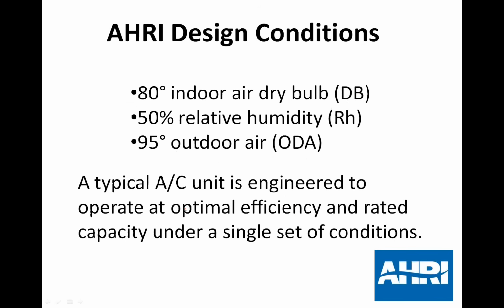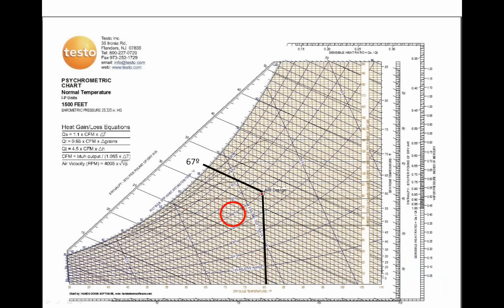When we look at ARI design conditions, okay, a fixed orifice system is engineered to operate under one set of conditions, just one set, that's it. 80 degrees indoor dry bulb, 50% relative humidity with 95-degree outdoor air entering a condenser. And that's the only target that the manufacturer has to engineer that system to operate under. So typically, those systems will operate a little over capacity or a little under capacity depending on the load conditions. The only time they'll operate at their optimal capacity is when they're running about 10 to 12 degrees of superheat at the evaporator coil. If they're not running near that 10 to 12 degrees of superheat, it's operating at a different capacity than it was engineered for. Now, that doesn't mean that it's supposed to operate at 10 to 12 degrees, because the superheat varies with load conditions. Now, let me show you some interesting stuff here to start with.